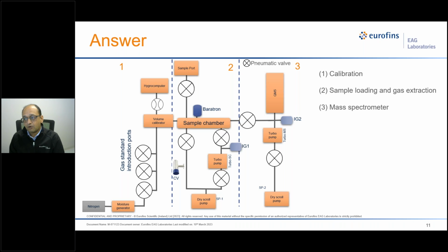To make this complex diagram a little bit simpler, we divided it into 3 sections, 1, 2, and 3. The first section mainly deals with the calibration of the equipment. As you can see, in the lower part, the first component that I would describe is the moisture generator. What is the function of this component? It is generating a known amount of moisture with a nitrogen mix. Nitrogen is supplied to this generator, moisture is added into this unit, and the final mix of moisture plus nitrogen is supplied to the valve system here, and that goes towards the volume calibrator.